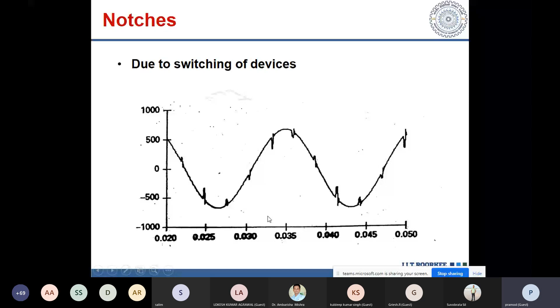If you have a 12 pulse converter, yes, there is a dominant 11th and 13th harmonic. And if you have a 24 pulse converter, there will be dominant 23rd and 25th. So power electronic converters are one of the main sources of injecting harmonics, or you can say drawing non-sinusoidal current from the source. And we have already seen this general expression, pn plus minus 1, for finding the order of harmonics, p being the number of pulses per cycle and n any integer. So in a 6 pulse converter, you have 5th and 7th. In a 12 pulse converter, you have dominant 11th and 13th, and so on.